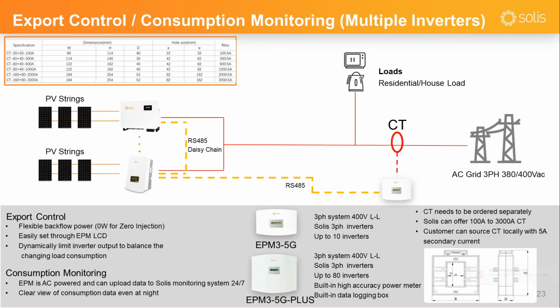And then again for the multiple inverter system: if you have a smaller commercial project where you need different models of three-phase inverters to be installed together and controlled together, we have two versions of EPM box for the three-phase system. One is EPM 3 5G, another is EPM 3 5G Plus. They can both support different models being connected together. The EPM 3 5G can connect up to 10 three-phase inverters, and the EPM 3 5G Plus version can connect up to 80 inverters. So this might be suitable for some medium size commercial projects.